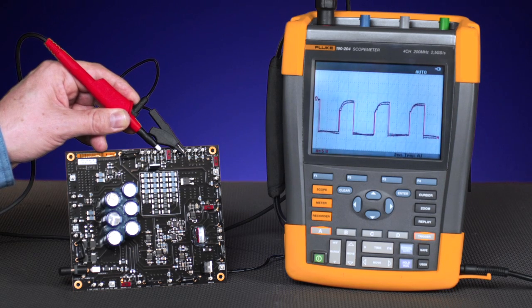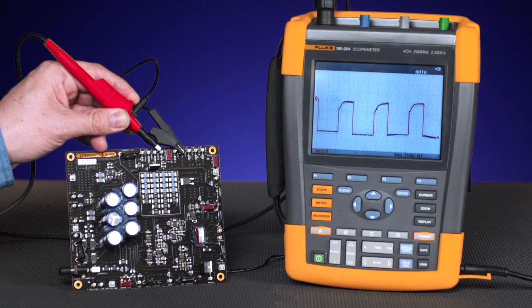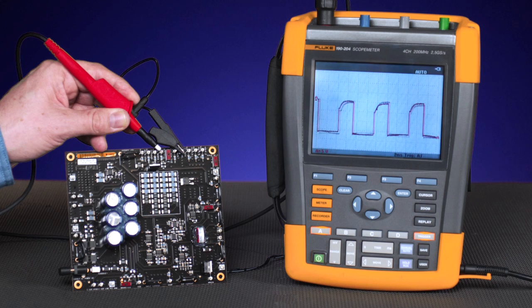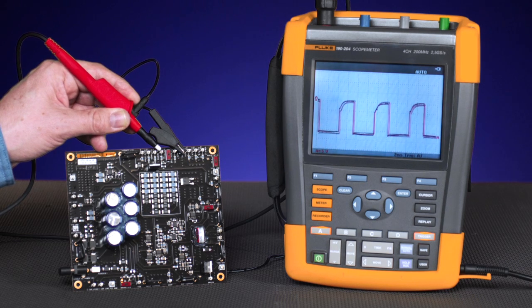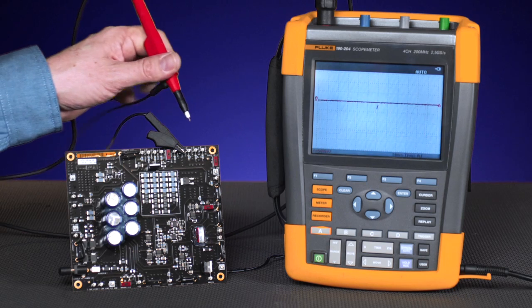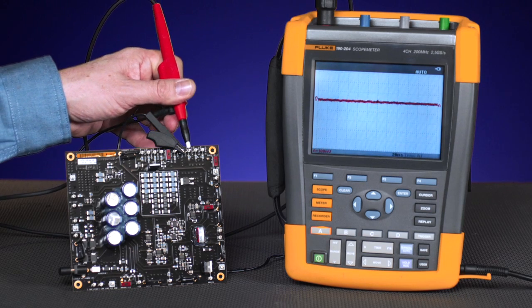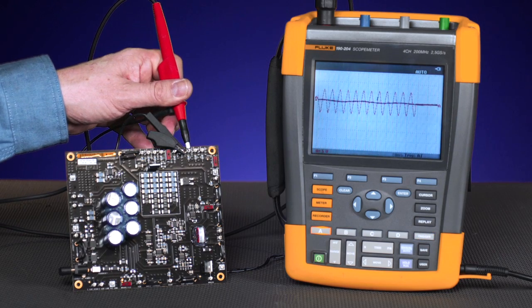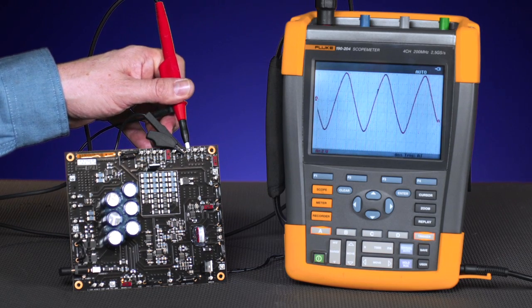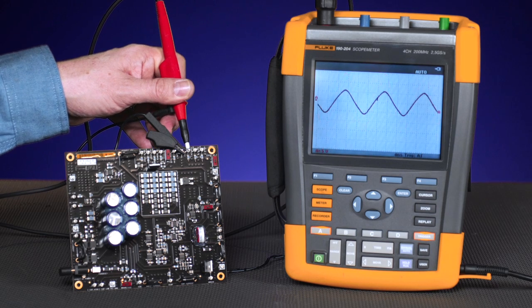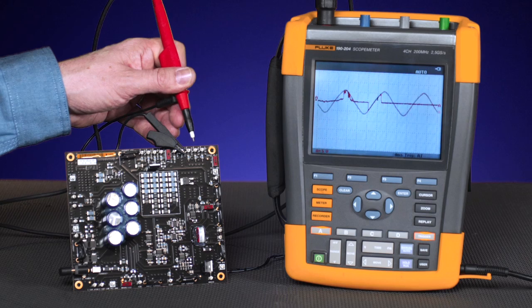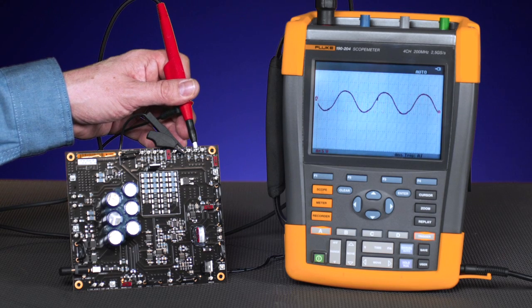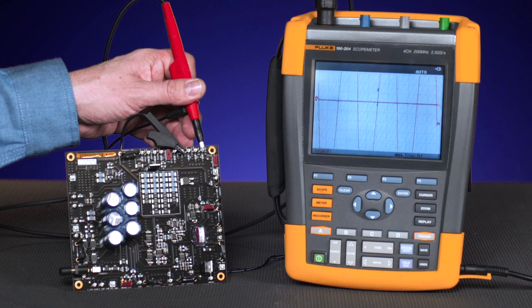After inspecting the switch, we can move to the three phase output signals, looking at the sine wave for any distortion. Looking at phase A, to phase B, and then to phase C.